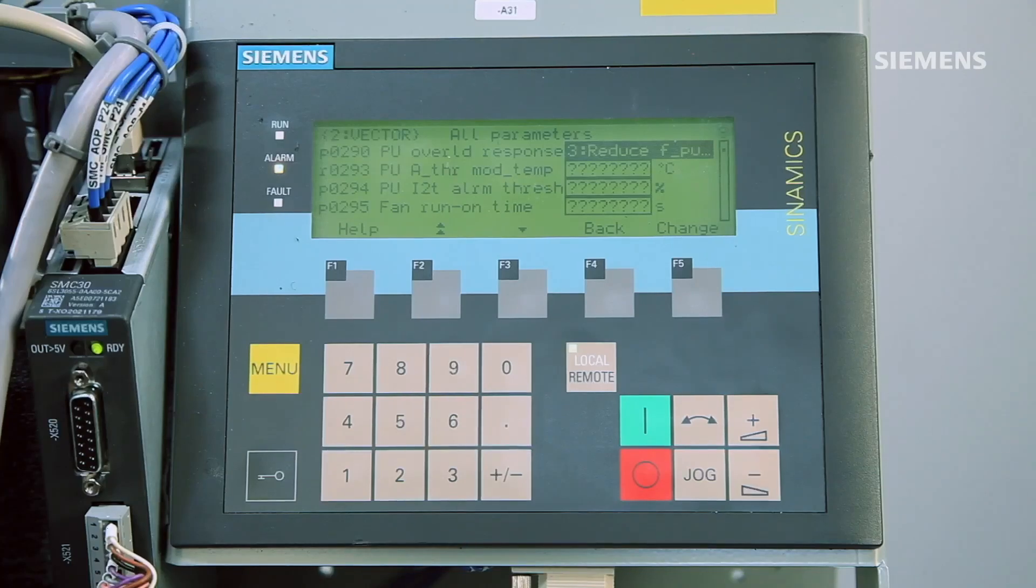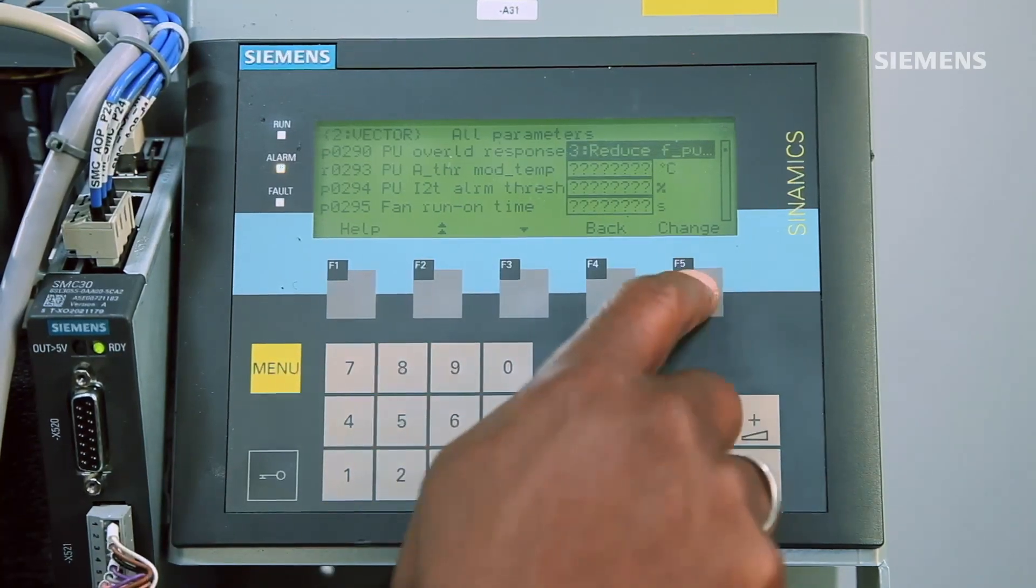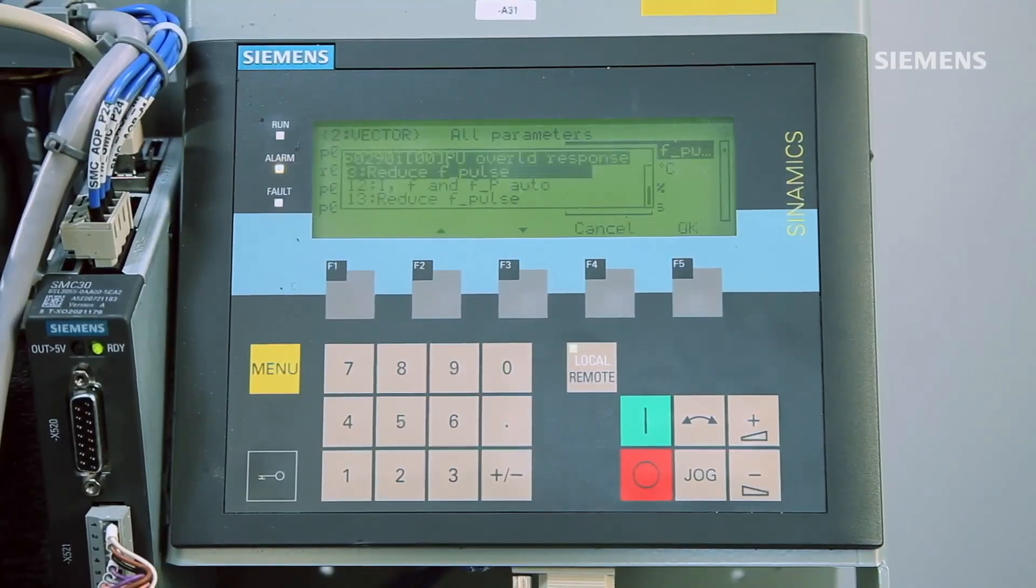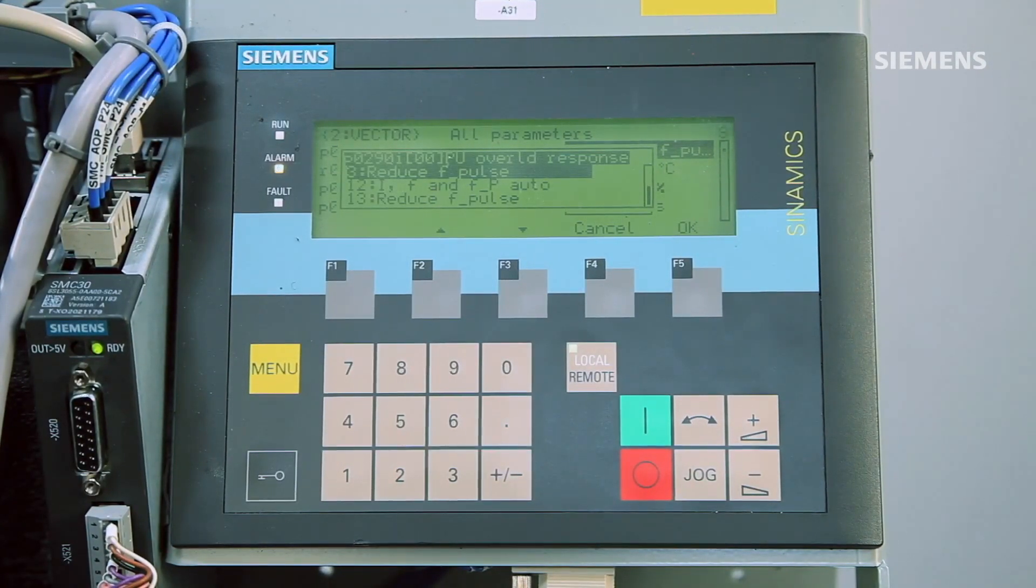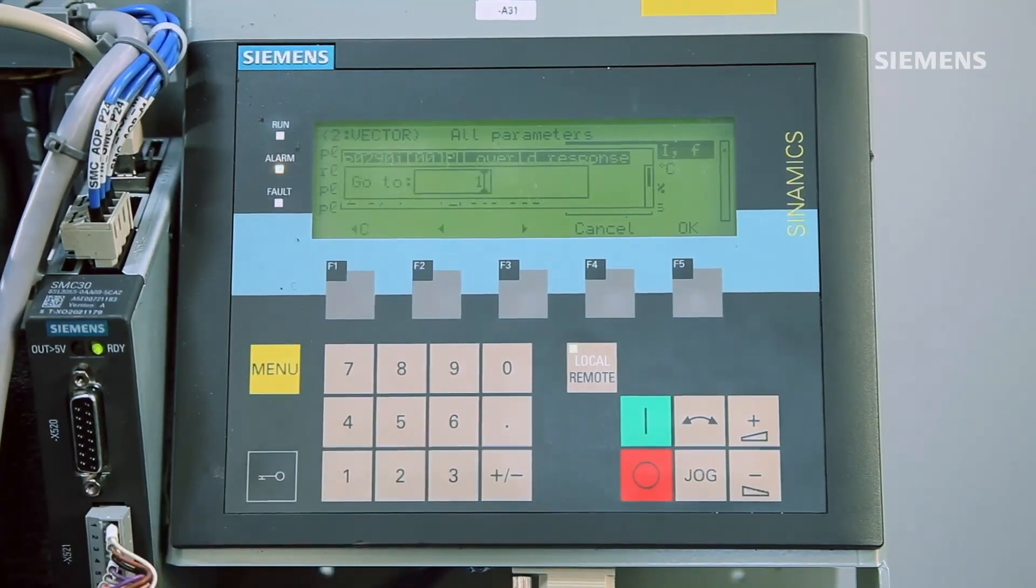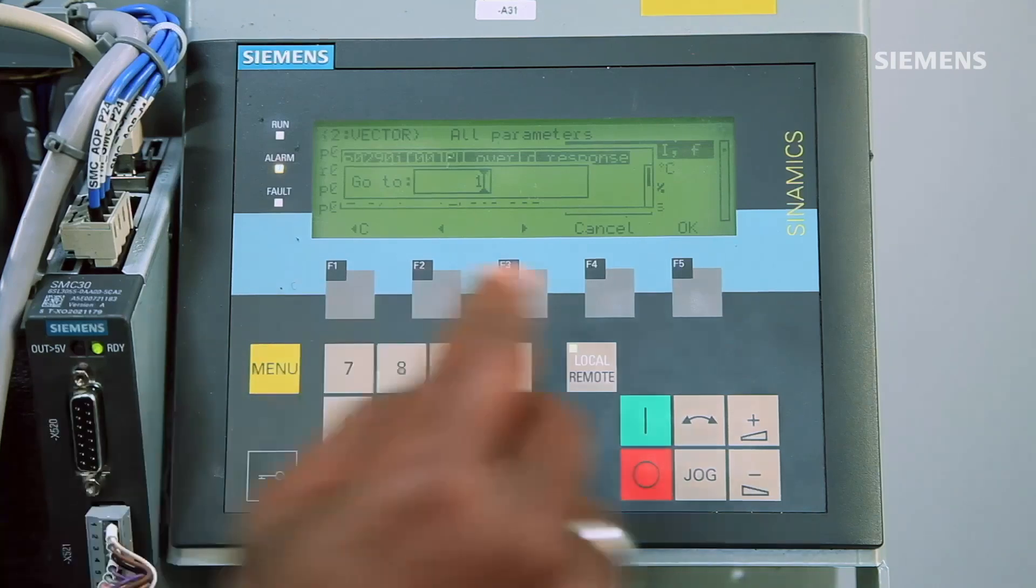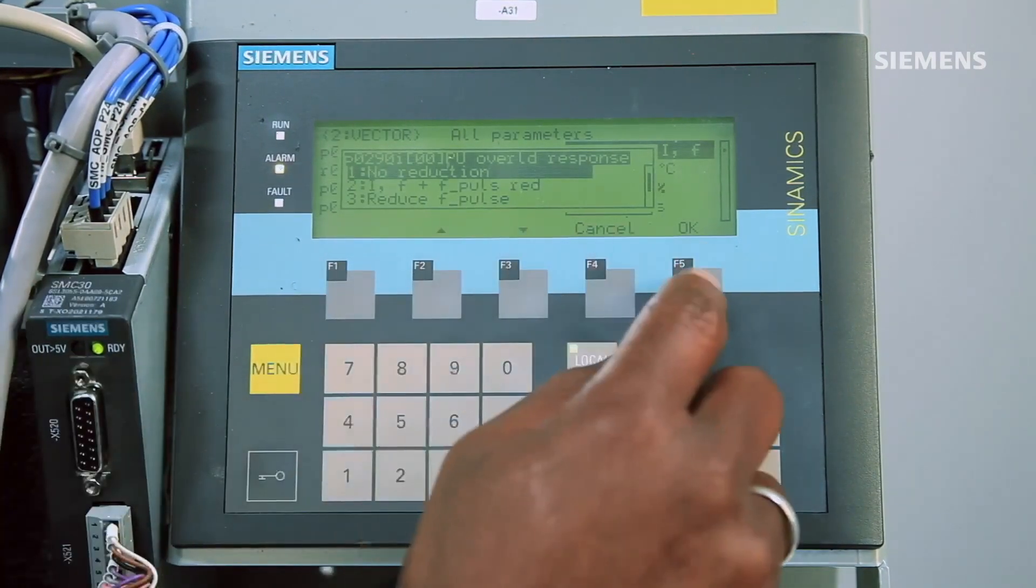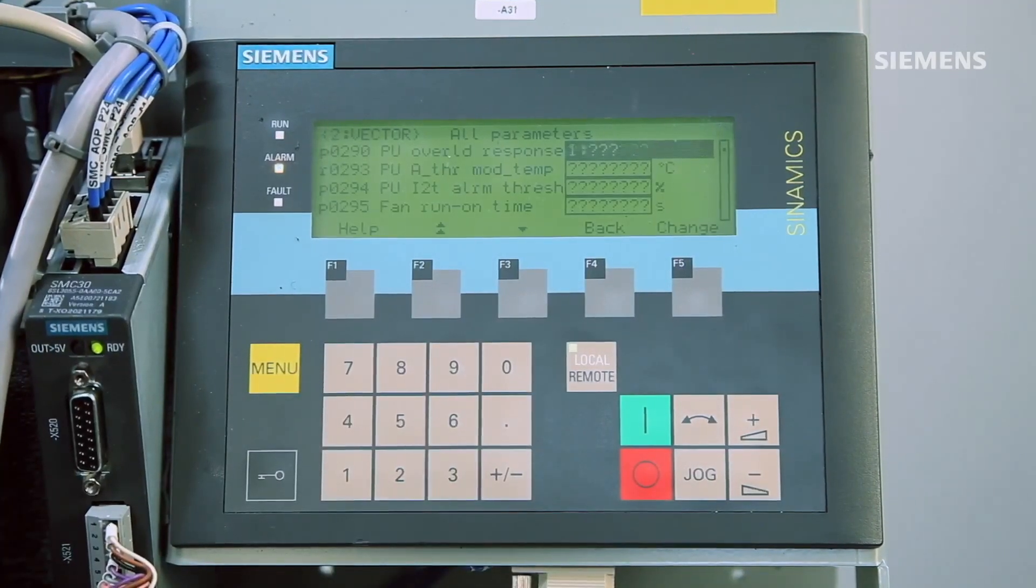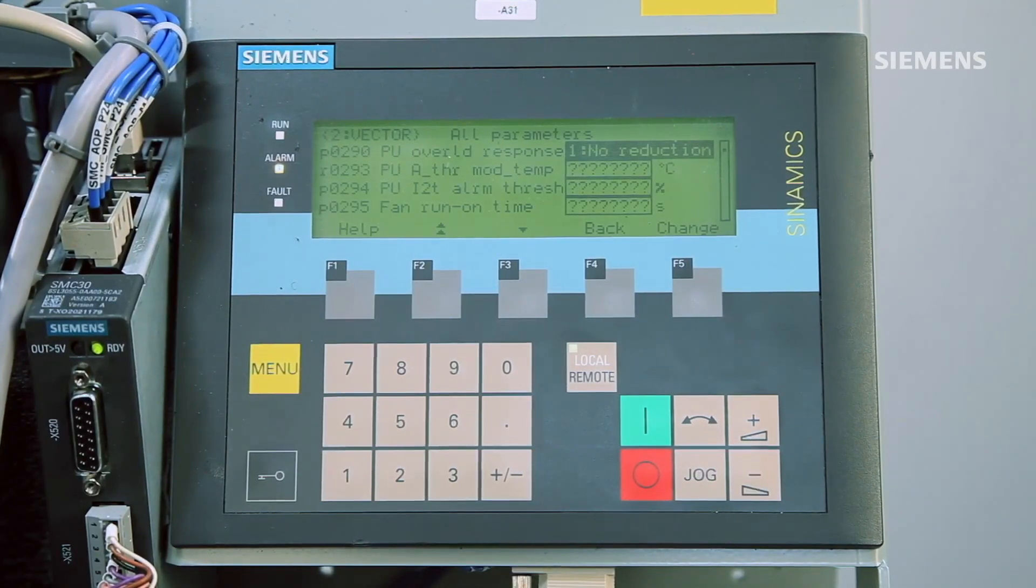Once you type in 290, it will highlight the options available. Hit the change button to select from the possible settings. The drive will respond differently depending on which setting you pick. If parameter 290 is set to 1, no thermal overload avoidance action will be taken. Instead, the drive will be permitted to overheat until a fault occurs and then the drive will shut down to prevent damage.